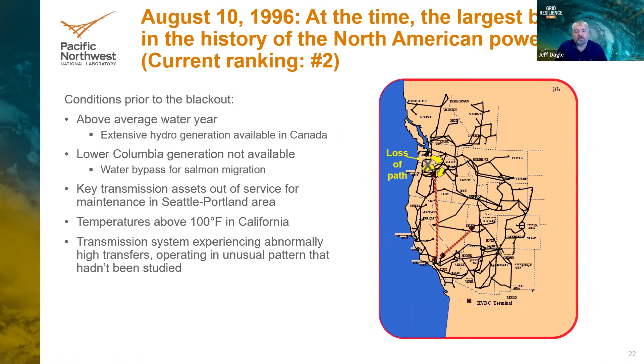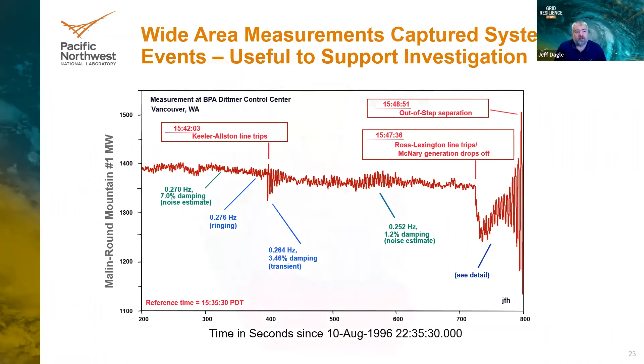Between Seattle and Portland, some electrical assets were out of service for maintenance, and through Eastern Washington the grid was under stress. We lost a couple of transmission lines about 5 minutes apart. Losing one is fine for that credible contingency I talked about earlier, but when you lose two, and then a generator trips off - the McNary hydro plant, right on the border between Washington and Oregon, not far from here in the Tri-Cities - that created an undamped growing oscillation that ripped the grid apart.